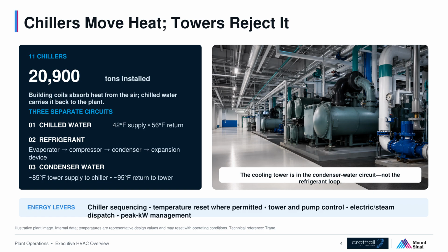Across 11 chillers, the installed capacity is about 20,900 tons. Efficiency depends on choosing the right machines, operating them near efficient part load points, managing lift, coordinating towers and pumps, resetting temperatures when conditions and clinical needs permit, and controlling peak electrical demand. The campus can also dispatch between electric and steam turbine chillers when equipment availability and utility conditions support it. Each loop has a different fluid and job, but performance appears only when the 3 circuits operate as one heat rejection chain.